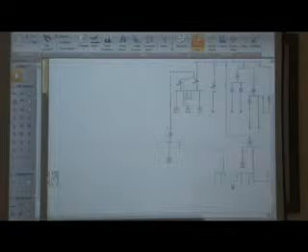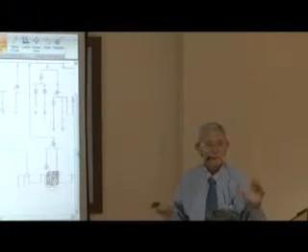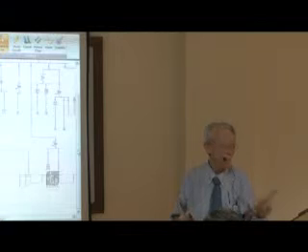And then you go through step by step, or maybe you want to include a little piece, say there's another group. A different crew is going to work on that little piece because we found out we had to do some switching. So now you have two groups of people working. One is working on the higher voltage, and one's working on the critical supply, and you have to work with both of them, and you need checklists and instructions for both of them. You can't be in two places at once. So you have to take each crew and say, group number one, we're going through the critical loads. This is what we're going to do. These are critical loads. Remember, folks, this is the nature of the process, and do you understand, and make sure.